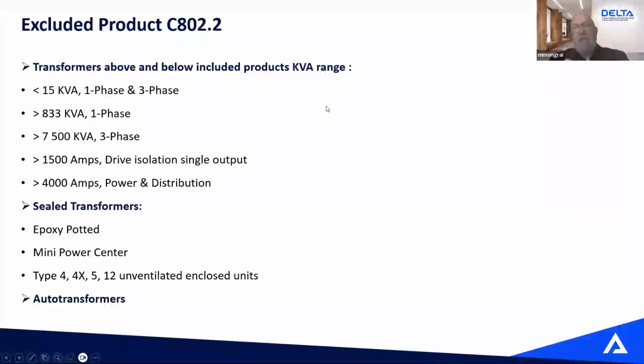So that being said, generally most transformers will be included in the minimum efficiency standard, besides the following. Single phase and three phase, anything below 15 kVA is excluded. Single phase, everything above 833 kVA is excluded. Three phase above 7,500 kVA is excluded. In regards to ampacity, power and distribution, anything above 4,000 amps will be excluded. What we call drive isolation, single output, anything above 1,500 amps is excluded.